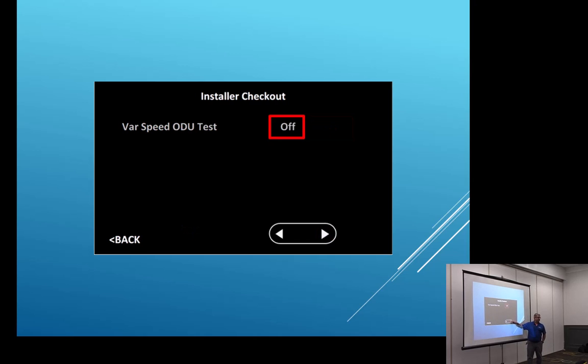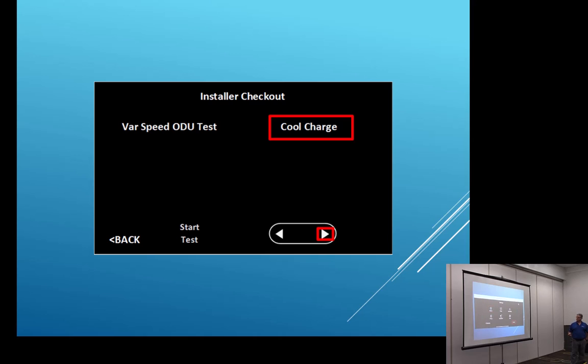I get this call a lot. They say, well, hey, I'm here, but it won't do anything. It just says off. I'm pressing the arrow, and it doesn't do nothing. That's because you need to touch up here first, on the screen where it says off. And then you can scroll over to cool charge or heat charge, and then you hit start test down here. Just remember, if we start the test, we have to what? Stop the test, or it's going to run forever, okay? So if you start the test, you have to stop the test.